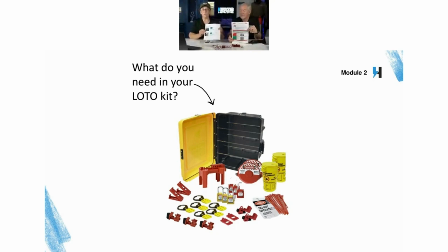You can see we've included tags on the equipment in our photos. Again, optional, not a requirement by OSHA or NFPA 70E, but certainly a best practice, to have tags on the isolation point. We mentioned valves, disconnects, or circuit breakers. Having a tag that identifies that isolation point where the lock is applied is, again, a best practice but not a requirement. Having those tags be durable enough to withstand the environment they're in is also important. If there's heat, humidity, or perhaps it's in a freezer with extreme cold conditions, we want to make sure all of these components can withstand the environment they're in.